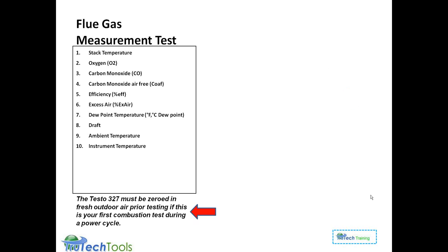Question came up, how is dew point temperature measured? Dew point temperature is not measured. It's a calculation based upon the type of fuel. The assumption is made that if the fuel is natural gas or propane or oil, the makeup of the fuel controls its dew point temperature based upon the chemical makeup of the fuel. So it would tell you the current dew point temperature for the fuel that you're burning.